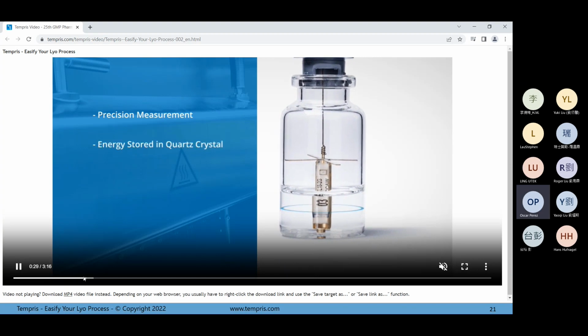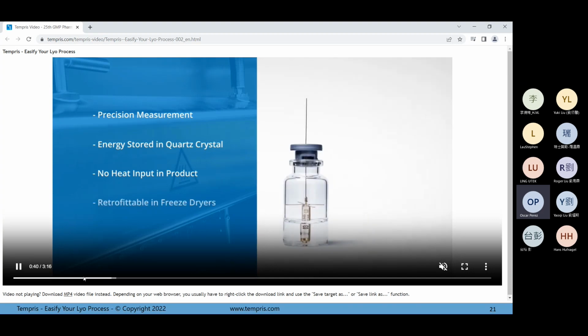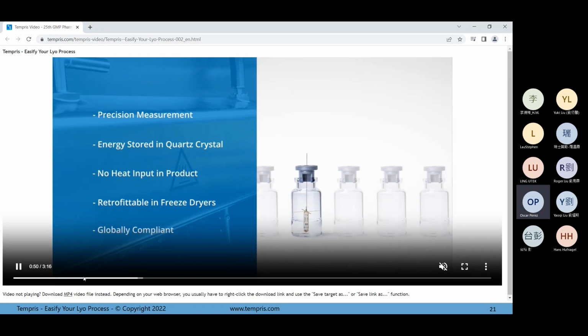Again, precise measurement, because we are measuring in the center and bottom, where the remaining ice is. Inside the sensor, we have the quartz crystal just in the bottom part, and we are not bringing any heat input to the product, as I mentioned before. We can use this technology for new applications, and we can also retrofit freeze dryers by installing the antennas and using our technology as well.